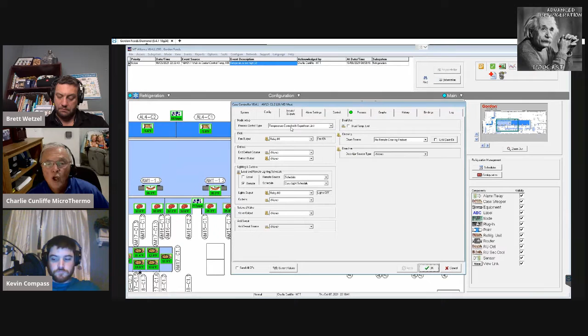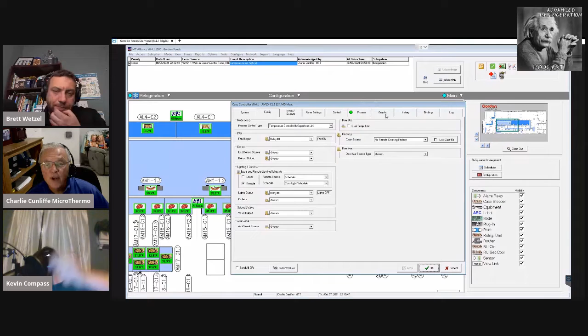Now again, with CO2, don't be alarmed. That might be a little bit higher than what you would expect, but with CO2 control, as far as superheat is concerned, it's really working in the background to prevent flood back. But as far as the configuration is concerned, it's temperature control priority with superheat as a backup. So that's why you might see superheats that are a little bit higher than one would imagine. But if you do your job right with Microthermo, so this is a 2 temperature, this has got a set 1 and a set 2, that's the kind of graph you want to see.